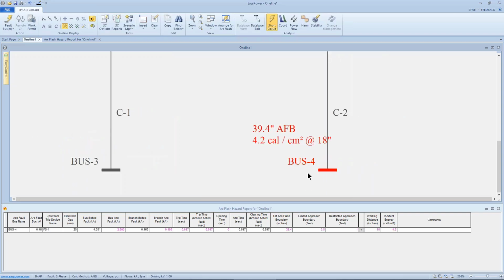If we go down to bus 4 and fault that, we still have 480 volts, we still have the same fuse, we still have the same air gap, but now the amount of available short circuit current is 4,351 amps, which we knew. According to IEEE, the maximum current an arc will draw is 2,803 amps. According to the data sheet for that manufacturer, it'll take almost 3/4 of a second to clear that fault with the fuse.